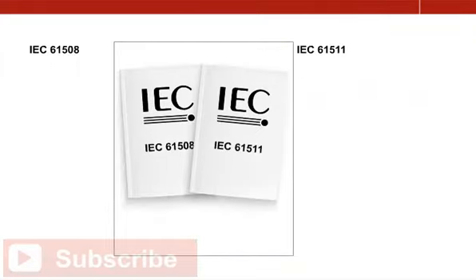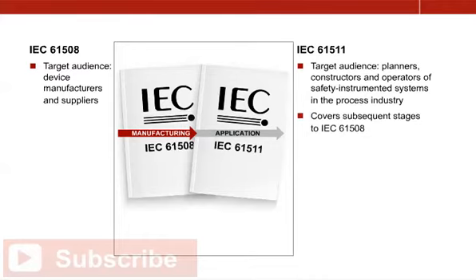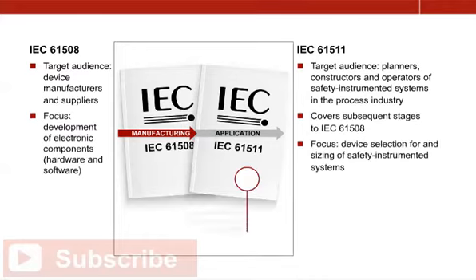The essential international standards dealing with functional safety in the process industry are IEC 61508 and 61511. While IEC 61508 is directed at manufacturers and suppliers of equipment, IEC 61511 is directed at users such as planners, constructors and operators of safety instrumented systems. As a result, both standards cover successive stages in the overall process. IEC 61511, which is the decisive standard for device selection and sizing, makes frequent references to the standard for developing electronic components, that is IEC 61508.